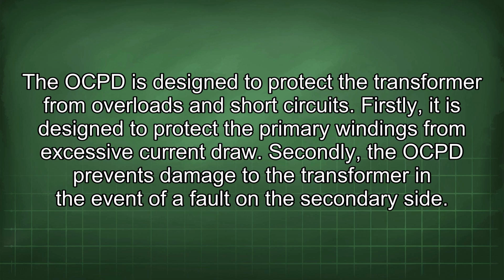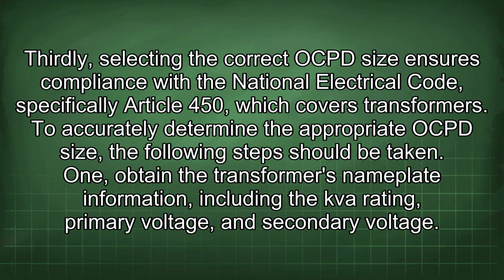Firstly, it is designed to protect the primary windings from excessive current draw. Secondly, the OCPD prevents damage to the transformer in the event of a fault on the secondary side. Thirdly, selecting the correct OCPD size ensures compliance with the National Electrical Code, specifically Article 450, which covers transformers. To accurately determine the appropriate OCPD size, the following steps should be taken.